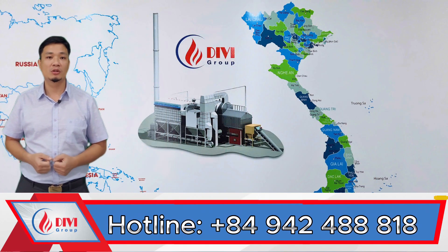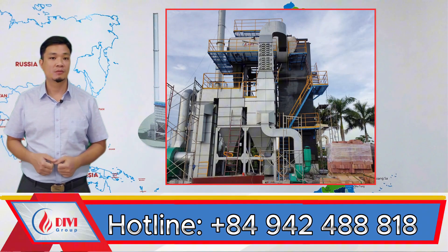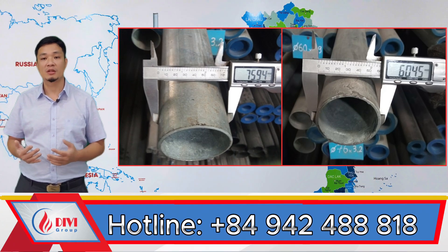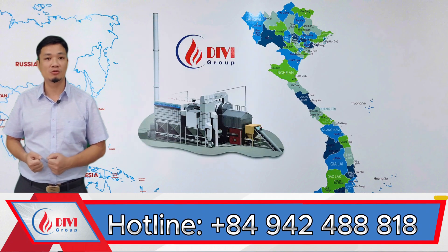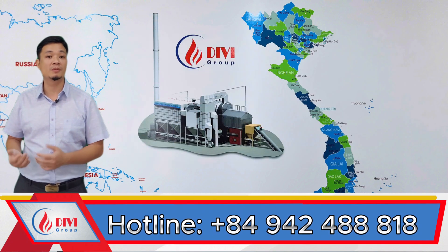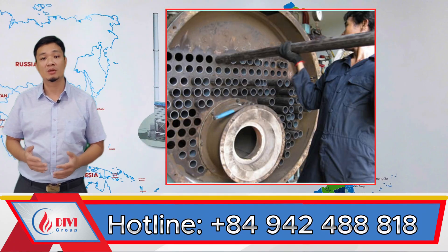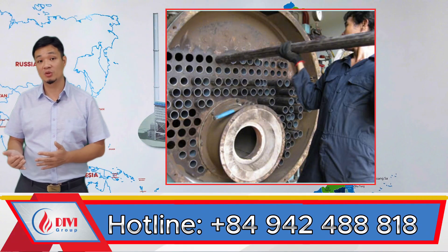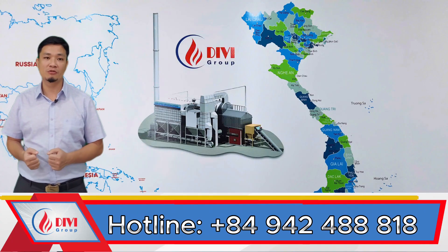Once we identified this root cause, we introduced a different solution — the combined water tube and fire tube boiler — to replace the older water tube systems. For the radiant section, we designed larger diameter steam-generating tubes, typically Ø76 mm or Ø60 mm. This significantly extended the boiler's operational life because it took much longer for scale to build up to critical levels. In addition, if any of the fire tubes in the convective section were damaged, we could replace several of them in less than two hours, thanks to a much simpler repair process. That meant our customers could restore production quickly, with minimal downtime.